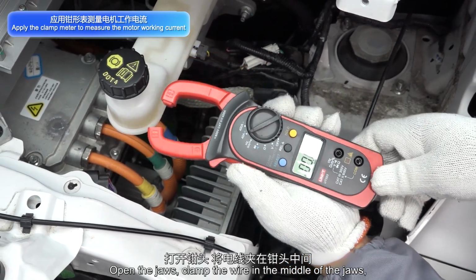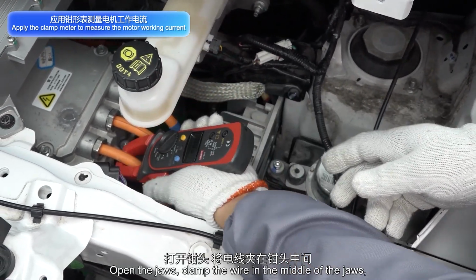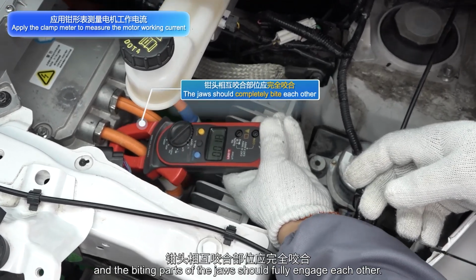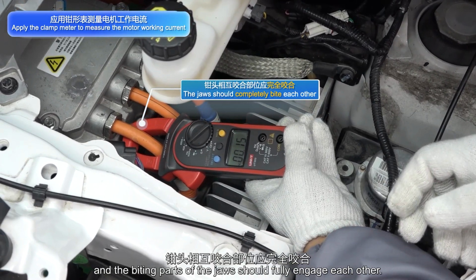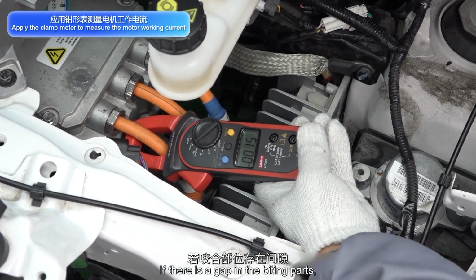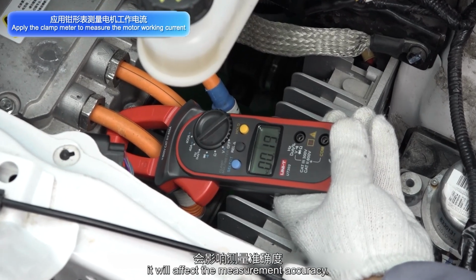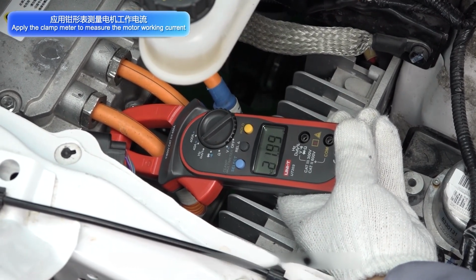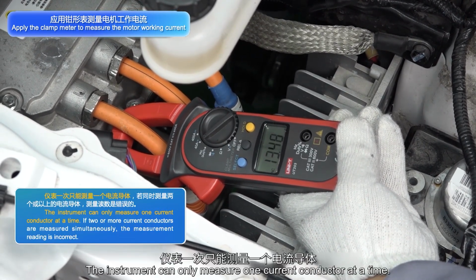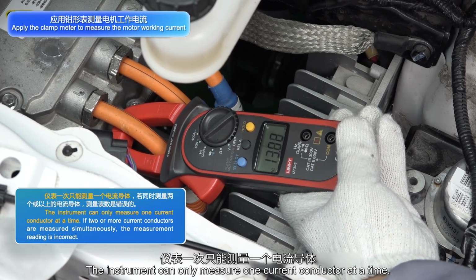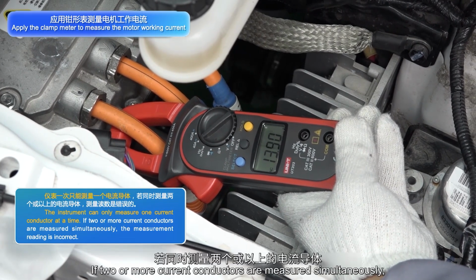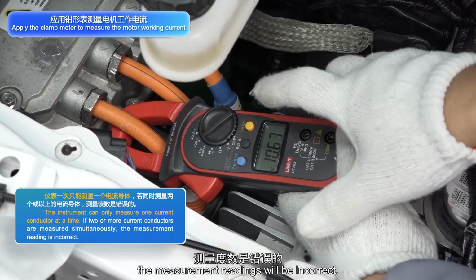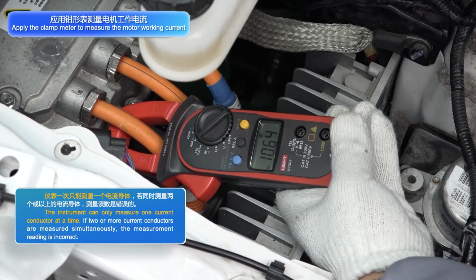Open the jaws, clamp the wire in the middle of the jaws, and the biting parts of the jaws should fully engage each other. If there is a gap in the biting parts, it will affect the measurement accuracy. The instrument can only measure one current conductor at a time. If two or more current conductors are measured simultaneously, the measurement readings will be incorrect.